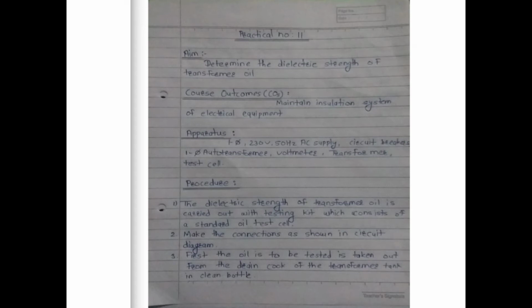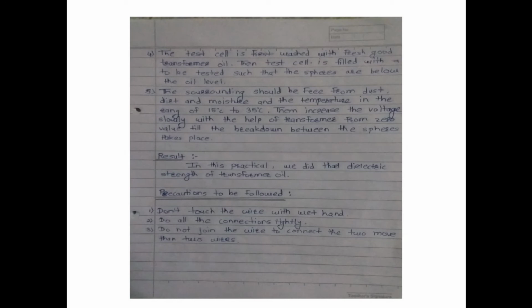So see this. First, the dielectric strength of transformer oil is carried out with a testing kit which consists of a standard oil test cell. Second, make the connections as shown in the circuit diagram. Third, first the oil to be tested is taken out from the drain cock of the transformer tank in a clean bottle. Then the observation table, fill this after performing the experiment. And the fourth point is that the test cell is first washed with fresh good transformer oil. Then the test cell is filled with the oil to be tested such that the spheres are below the oil level.